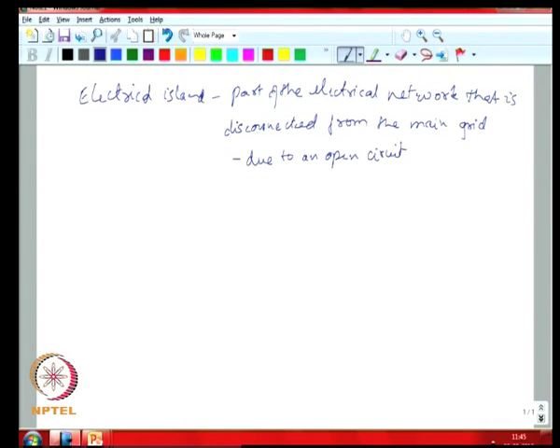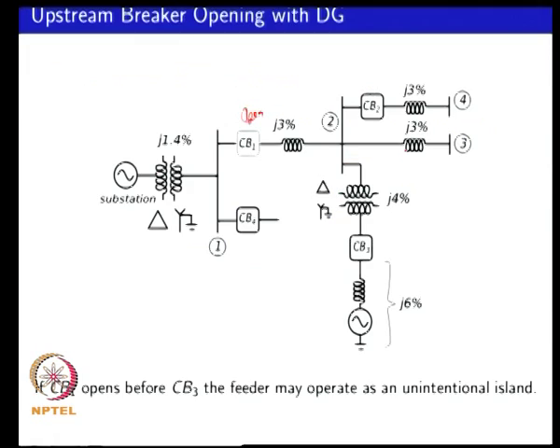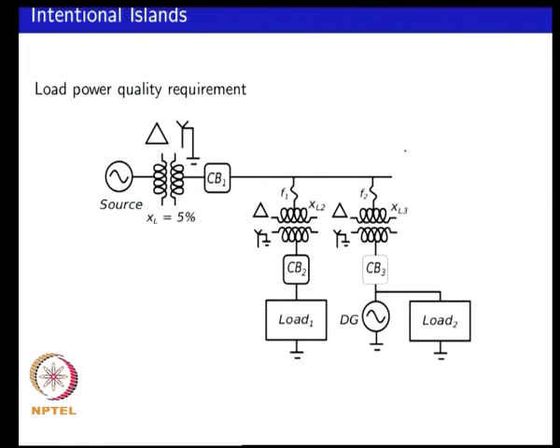An electrical islanding situation can be of two varieties: you can have an intentional island or an unintentional island. For an intentional island, the reason one would typically have it is for power quality reasons. The idea is you open a breaker which connects to the main grid, and then your source can actually feed a local load when there is poor power quality in the main grid. So you want to isolate yourself from the main grid and continue to feed higher quality power to your load.